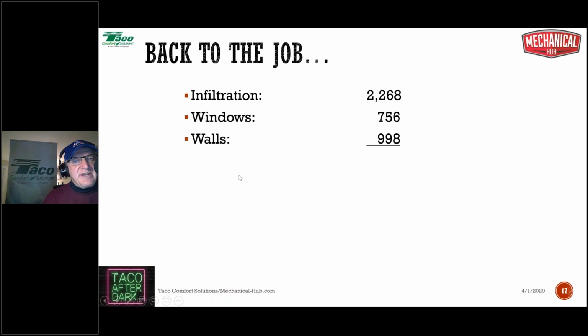Let's go back to the job and total it all up. I've got infiltration heat loss of 2,268, windows of 756, and walls of 998. That means for this room we're talking about 4,022 BTUs - that's BTUH/R, BTUs per hour required. That's what we need to deliver to that room under design conditions to keep it at 70 degrees.